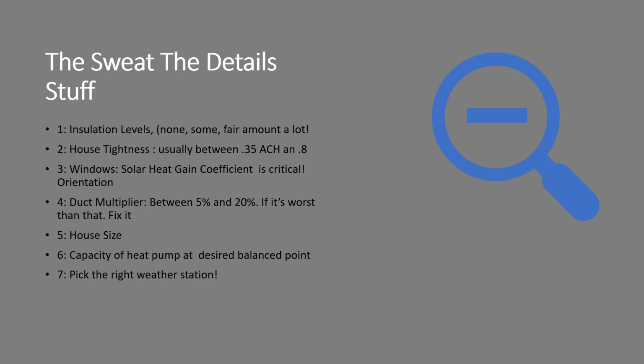House tightness here in the Northwest, it typically ranges from 1/3 of an ACH up to 0.8. New construction is probably going to be closer to 0.2. If your software tells you have an ACH of 2, something is probably wrong. That would be a barn with the doors open on a windy day. Windows, our solar heat gain coefficient is absolutely critical. In the Northwest, if you know the U value, that say you have a U value of your window of 0.4, the solar heat gain coefficient is also pretty close to 0.4. A lot of software out there guesses a little too high at the solar heat gain coefficient, which pads the cooling load a little too much.